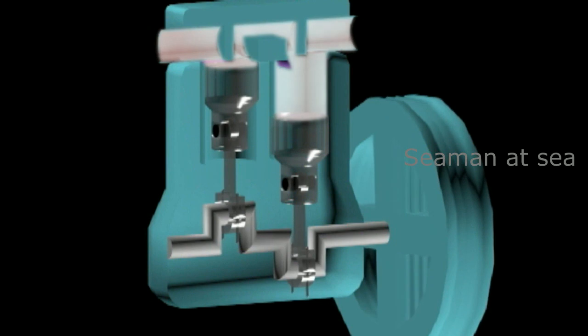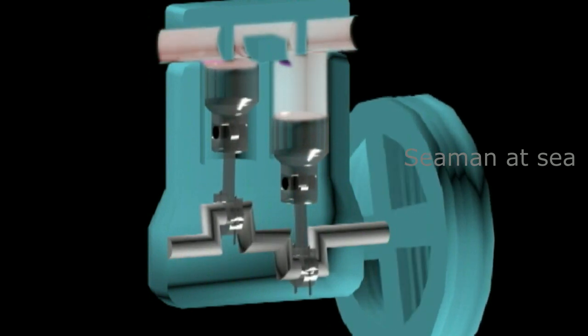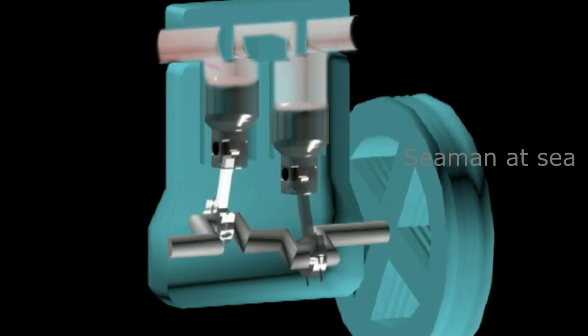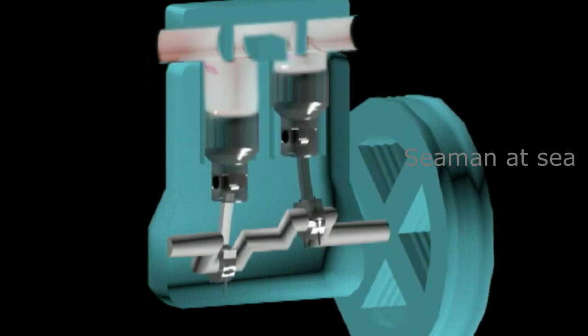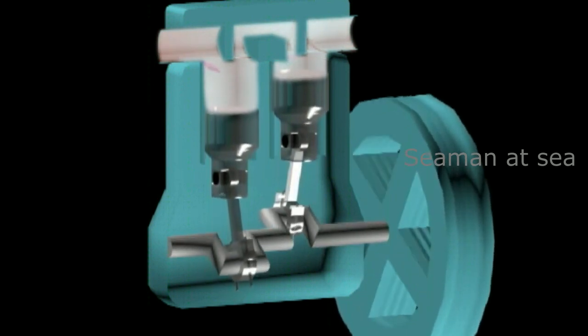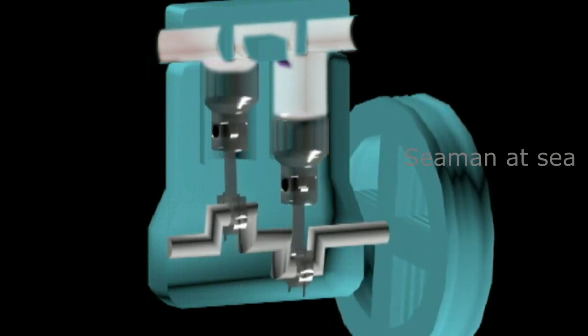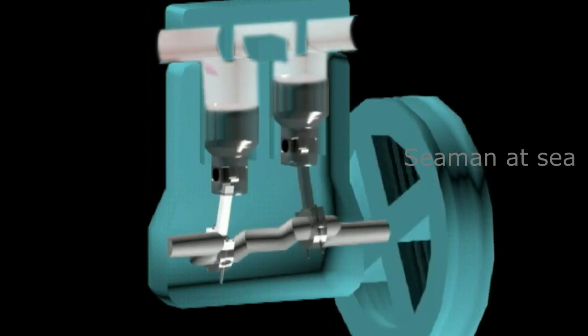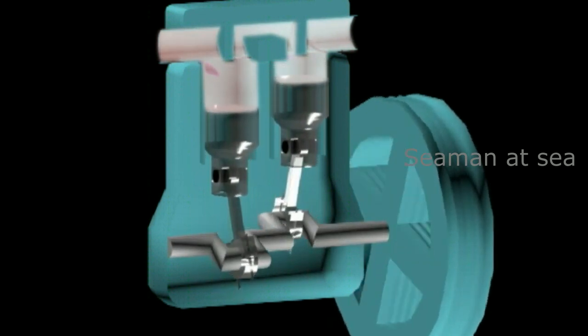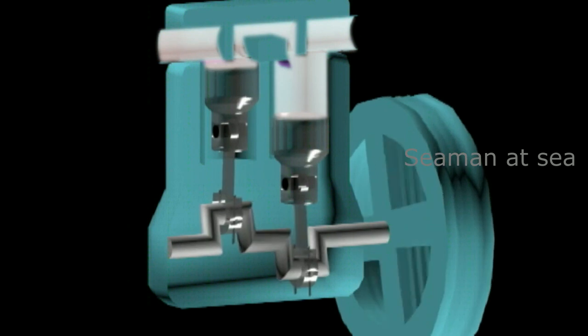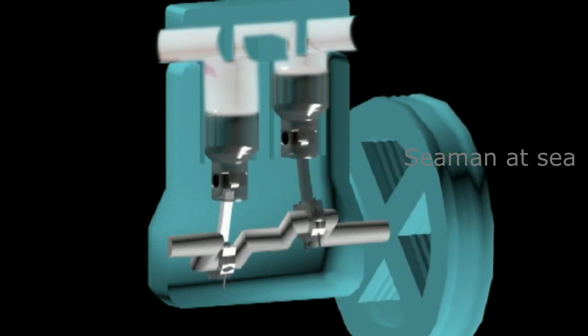The compressor also promotes circulation of the refrigerant by pumping it around the system. On a suction stroke where the piston is moving downward, the clearance space between the piston and the cylinder head will expand. The drop of the pressure will open the plate-type suction valve and forces the refrigerant to enter the chamber until such time as the suction valve closes.